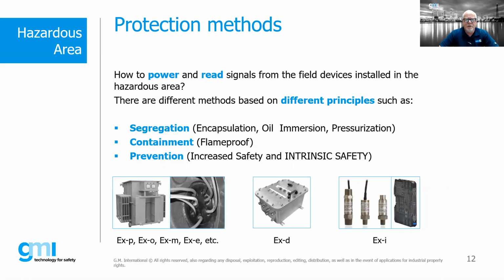There are different protection concepts that we use with regards to hazardous locations, both mechanical and electrical. The main ones that you're probably familiar with are flameproof, which is EXD, and EXI, which is intrinsic safety. And then there are other protection concepts as well: EXP, pressurization; O, oil immersion; M, encapsulation; and increased safety. So there's a significant number of different protection concepts out there, but they basically fall into three major areas.